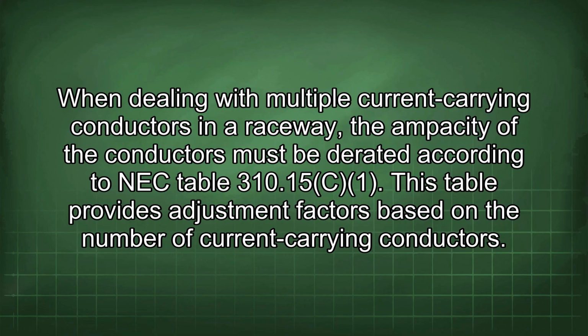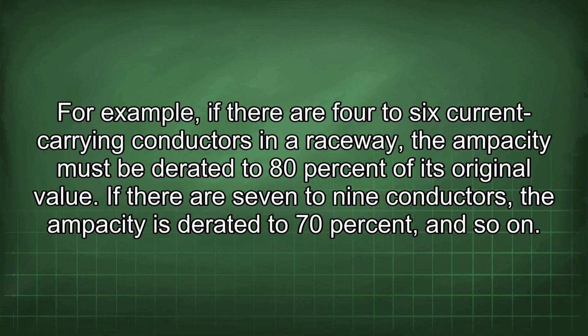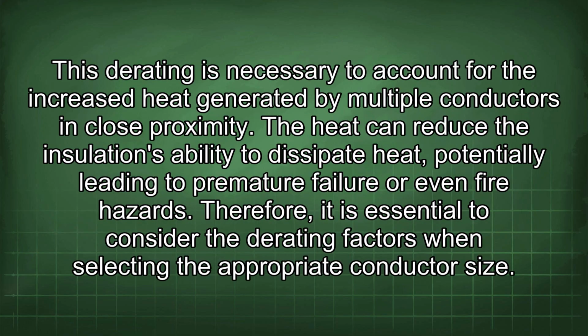When dealing with multiple current-carrying conductors in a raceway, the ampacity of the conductors must be derated according to NEC Table 310.15. This table provides adjustment factors based on the number of current-carrying conductors. For example, if there are 4 to 6 current-carrying conductors in a raceway, the ampacity must be derated to 80% of its original value. If there are 7 to 9 conductors, the ampacity is derated to 70%, and so on. This derating is necessary to account for the increased heat generated by multiple conductors in close proximity. The heat can reduce the insulation's ability to dissipate heat, potentially leading to premature failure or even fire hazards. Therefore, it is essential to consider the derating factors when selecting the appropriate conductor size.